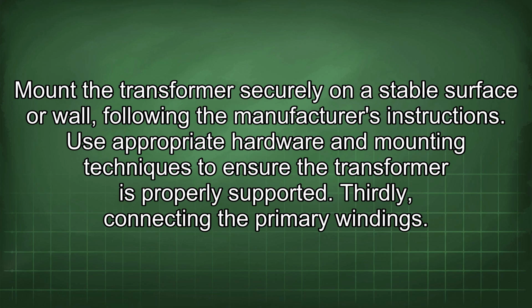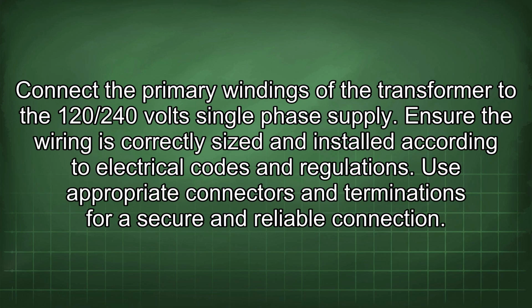Thirdly, connecting the primary windings. Connect the primary windings of the transformer to the 120/240 volt single-phase supply. Ensure the wiring is correctly sized and installed according to electrical codes and regulations. Use appropriate connectors and terminations for a secure and reliable connection.